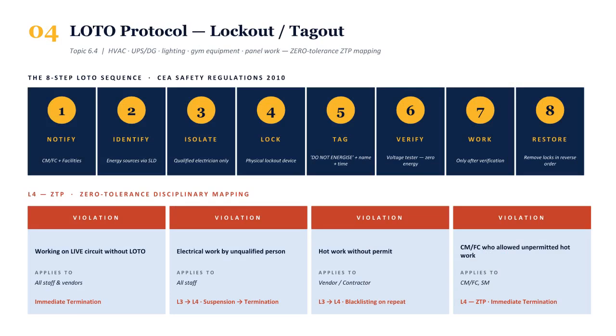Topic 4. LOTO. Lockout Tagout. This is the mandatory energy isolation procedure for every electrical maintenance activity at TeamFit: HVAC, UPS, DG, lighting, gym equipment, panel work. 8 steps in strict sequence. Step 1. Notify CMFC and facilities. Step 2. Identify all energy sources using the single line diagram, the SLD. If the SLD is missing, work does not proceed.